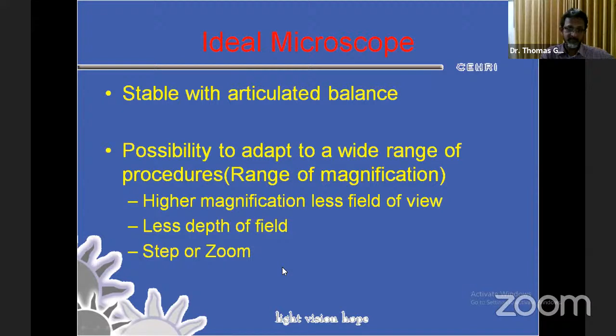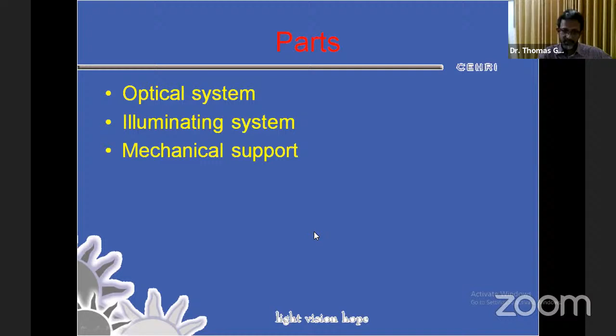Your magnification can be a step or a zoom system. The parts of a microscope would be the optical system, illuminating system, and of course the mechanical support. Optical system quality would decide the quality of viewing that you're going to get through the microscope. For the illuminating system, typically we have a coaxial illumination that would give a good red glow and is useful for intraocular surgeries. Whenever you want to see anything inside the eye, you're peeping through a small window, and you need a light source that is not casting shadows, so you need coaxial illumination. Whereas on the surface, you are better off with an oblique illumination. And there's one more reason why we should tend to go for an oblique on the surface: these light sources are quite strong, and if you have a long surgery, you can actually burn the macula.